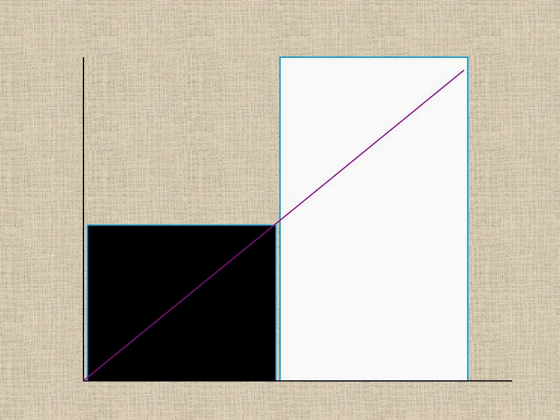In its simplest form, it could decide that half the signals coming back at the lowest signal strengths would all be colored black as pixels on the screen, and the top 50% of signal strengths coming back would all be colored white on the computer screen. This means that the pixels would only be black or white, and would give an incredibly high contrast picture, which would be useful for things like vascular scanning, where you're just trying to differentiate between the inside and outside of a blood vessel.